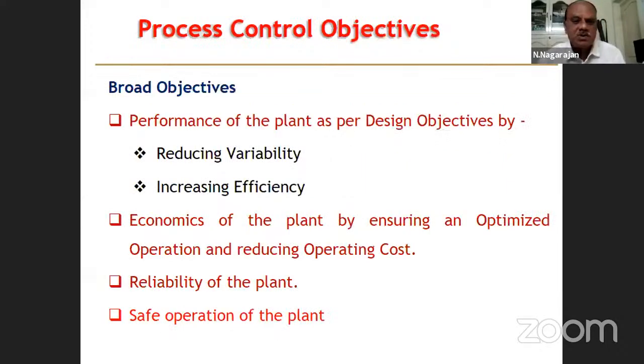So the broad objectives of process control are performance of the plant as per design objectives, that is, reducing the variability. For any parameter, we keep a range of operation and we need to keep the range very narrow and minimize the variation in the parameter so that the process is steady, increasing the efficiency. So by using process control effectively, you can increase the efficiency of the process.